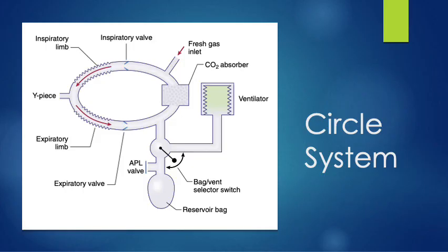So here's a picture starting in the upper right-hand corner at like 1 o'clock. You see number 1, fresh gas inflow. You see moving counterclockwise, so moving to the inspiratory valve. There's the inspiratory limb. Here's the Y piece. A key learning or takeaway here is if you have competent or working unidirectional valves, dead space will begin, or apparatus dead space begins distal to the Y connector or any tube or mask between it and the patient's airway.